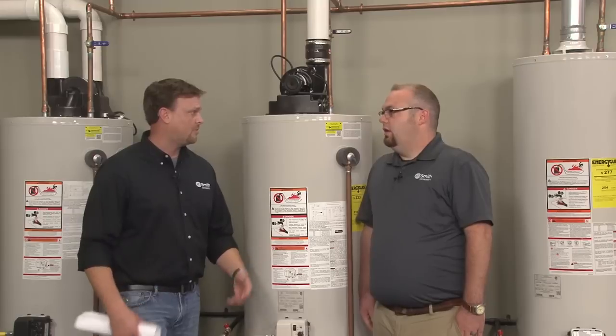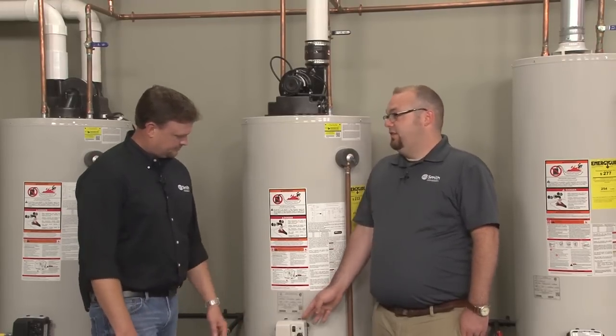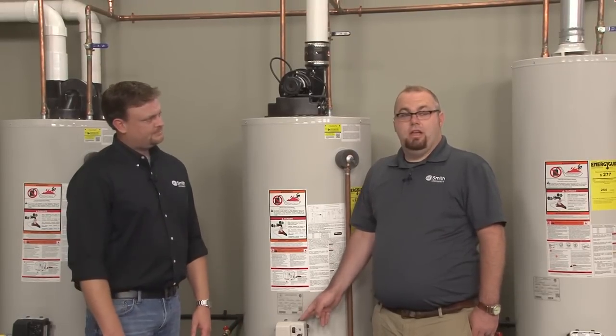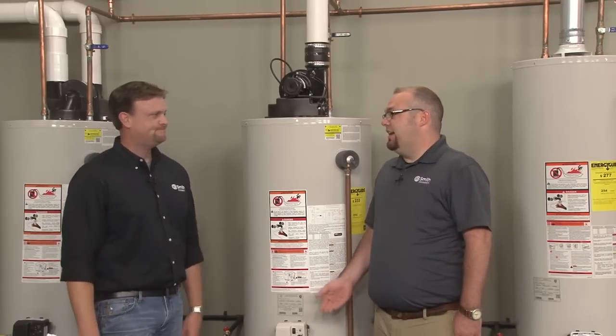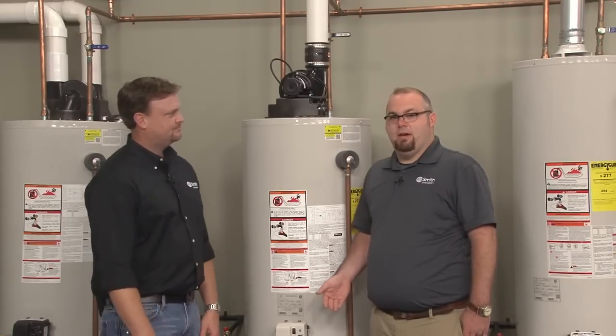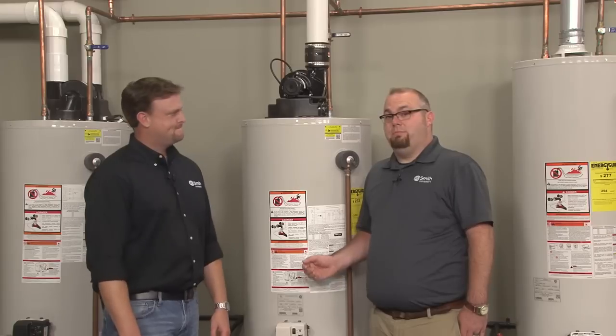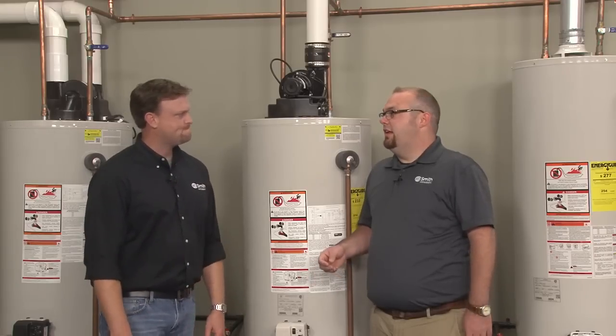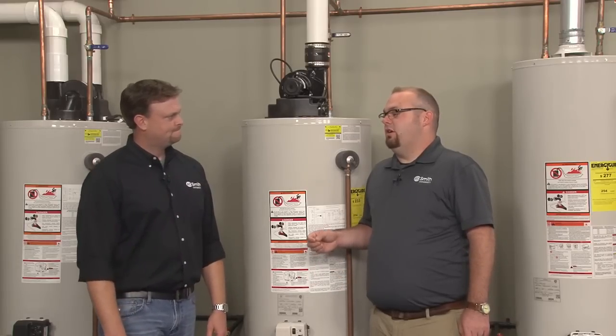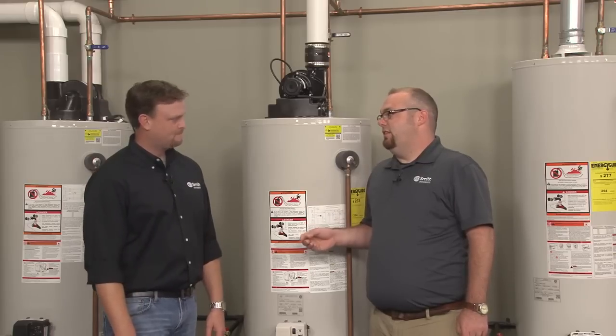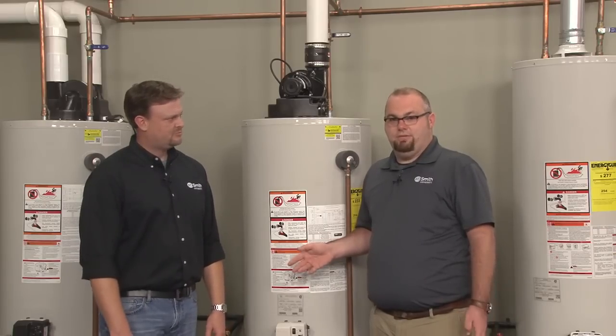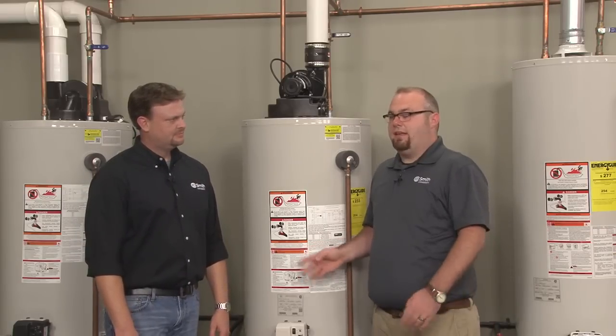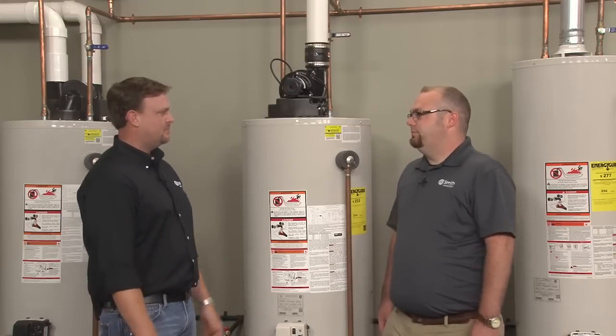And everything that we've said about this code, the 6.1 on the Honeywell, is also true for error code 6 on IntelliVent, which is signified by the vacation light, the A and B light lit up. So your first light, and then I believe it's going to be your 4th and 5th light. Right. So vacation, A and B, it's going to be the same thing. If you see a flame, clean the flame sense rod, it usually fixes it. If you don't see a flame, check gas. Because the sequence of operations is pretty much the same on that one.